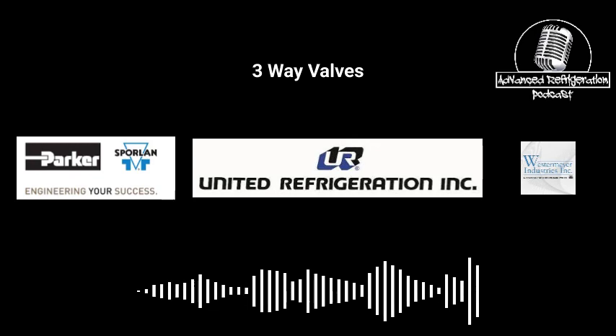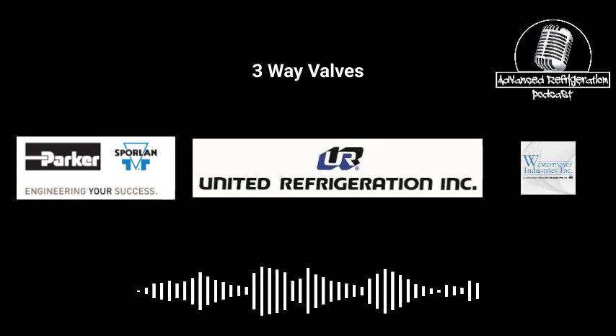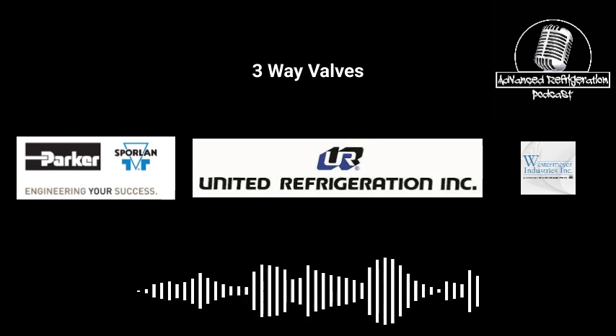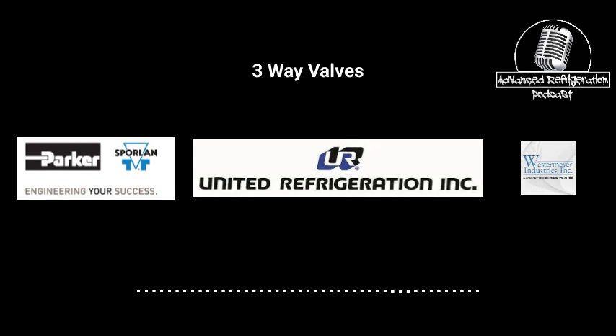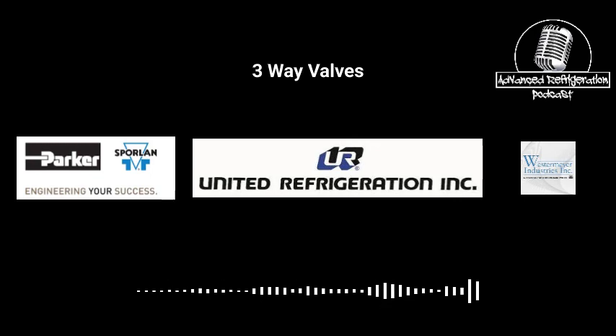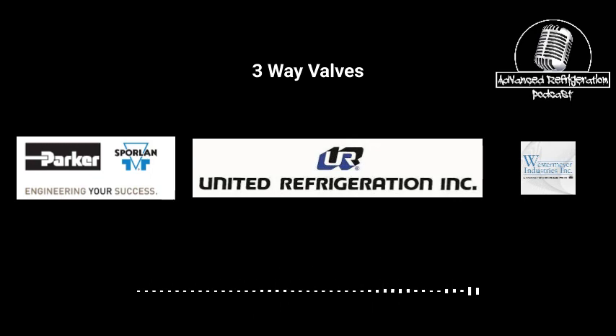Now, when you're looking at three-way valves, like Brett said, the two main valves you're going to see is a split condenser valve and a heat reclaim valve. Now, the two major differences in these valves is one works either or, meaning it's either going out of one side of the three-way valve or the other side of the three-way valve. That would be a heat reclaim valve. So it's either going to be going to the heat reclaim side or to the condenser side or to the outlet of that valve, the normally open outlet.